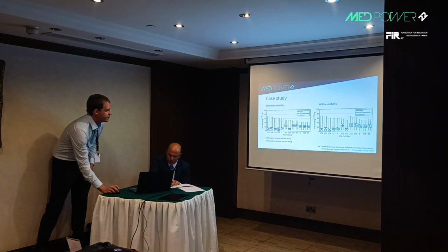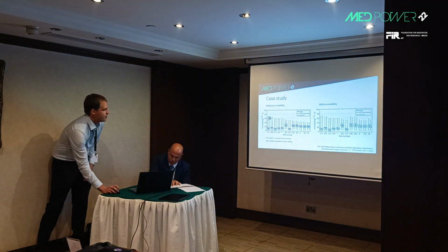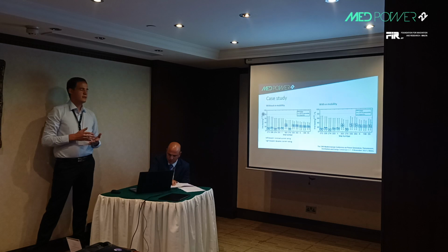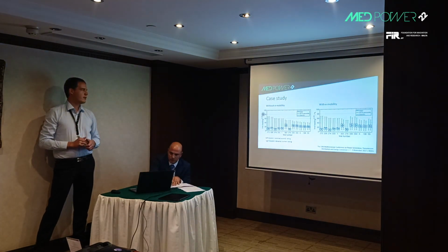Here it decreased because the mean value decreased, and the maximum value also decreased for most of the lines. Only for some lines the maximum value increased. This is because in summer the permissible value for the current rating is lower than the nominal current rating.